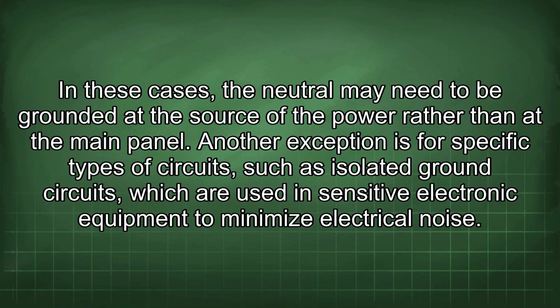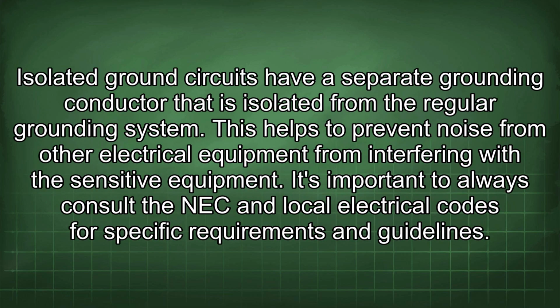main panel. Another exception is for specific types of circuits, such as isolated ground circuits, which are used in sensitive electronic equipment to minimize electrical noise. Isolated ground circuits have a separate grounding conductor that is isolated from the regular grounding system. This helps to prevent noise from other electrical equipment from interfering with the sensitive equipment.